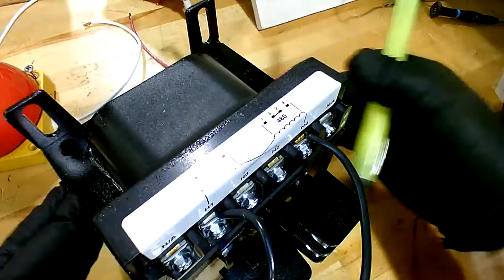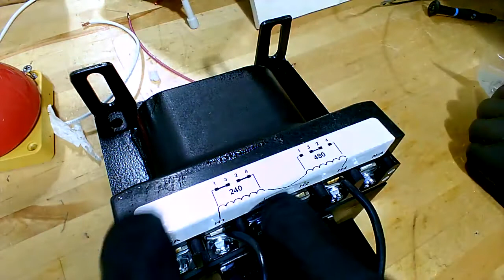The transformer has a dual winding on the primary, so those little squiggly lines there, those two coils that are in this primary, have to be in parallel for low voltage. They have to be in series for high voltage. Okay, and we'll get into that later as far as on the board. The windings have to have 240 across each one. And you put them in parallel, and your source voltage is 240. There's 240 across each one of the windings.